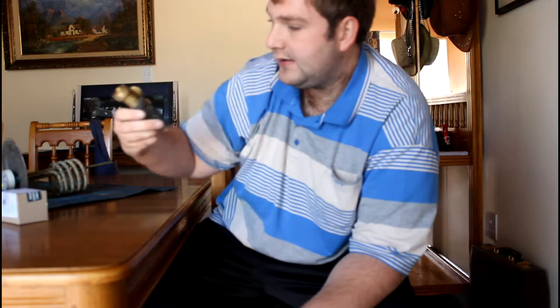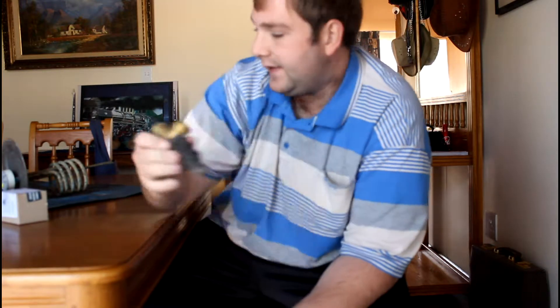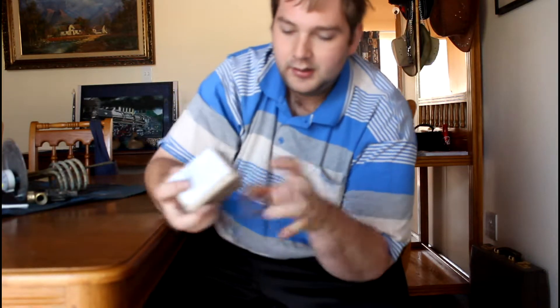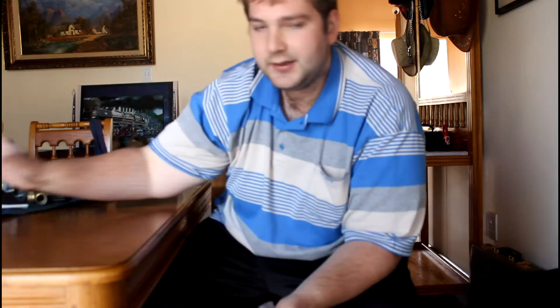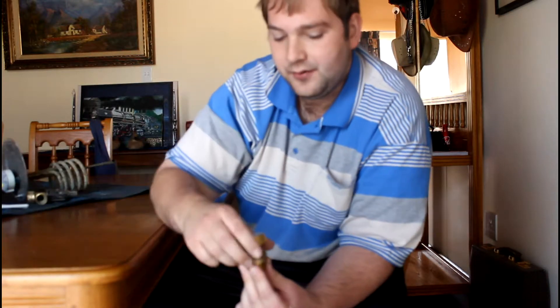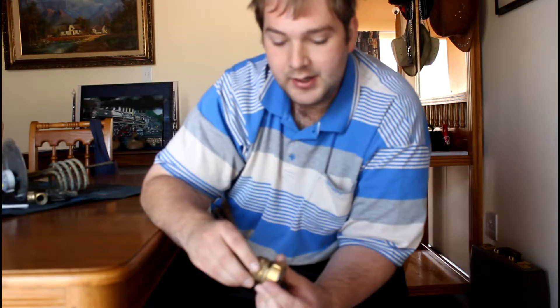These are the drain cocks from QuickCut as well. And then I have this vacuum breaker from Cobra. QuickCut's vacuum breakers aren't that bad, it's just if you put them in the sun they have plastic, so they tend to burn or break. Cobra is fully brass.